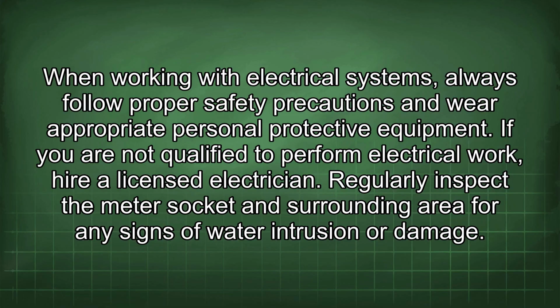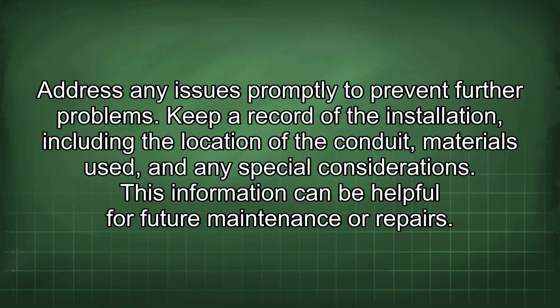Regularly inspect the meter socket and surrounding area for any signs of water intrusion or damage. Address any issues promptly to prevent further problems. Keep a record of the installation, including the location of the conduit, materials used, and any special considerations. This information can be helpful for future maintenance or repairs.